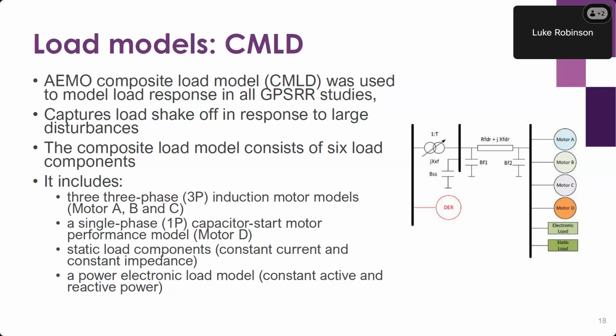A static load, which is represented by a ZIP model. This doesn't have any tripping parameters, but will scale the active power with the bus voltage. And finally, a power electronics component, which includes undervoltage tripping behavior, but apart from that is relatively insensitive to voltage or frequency.